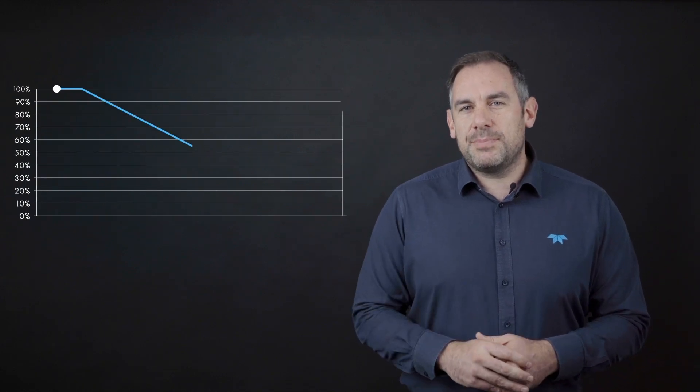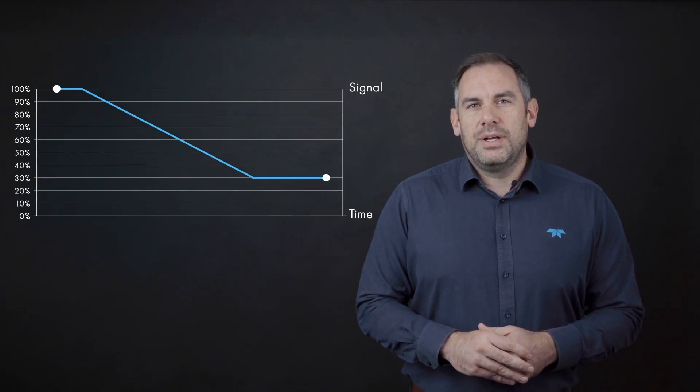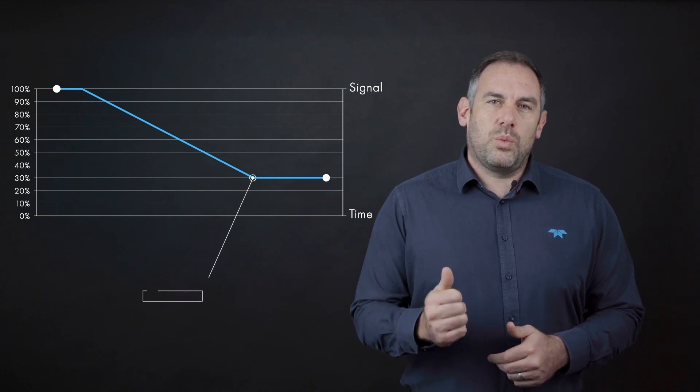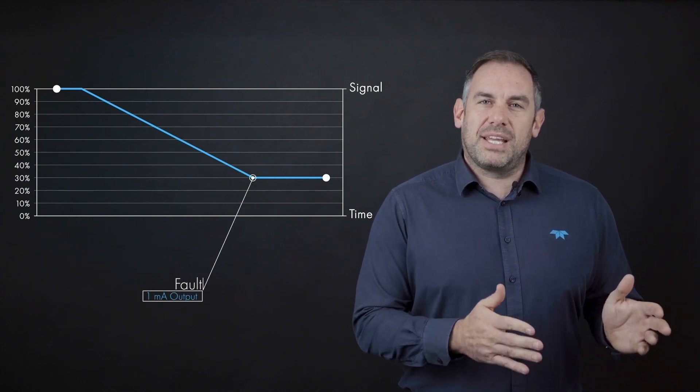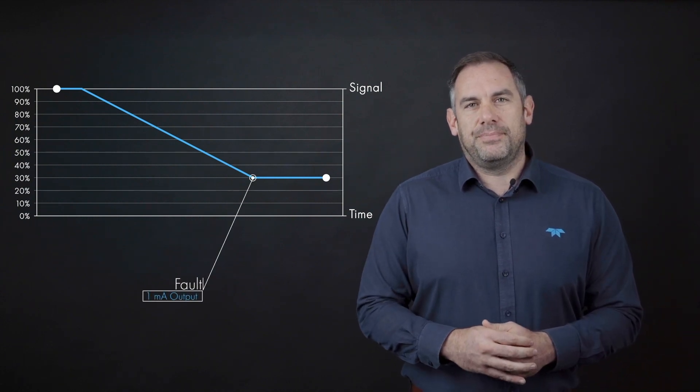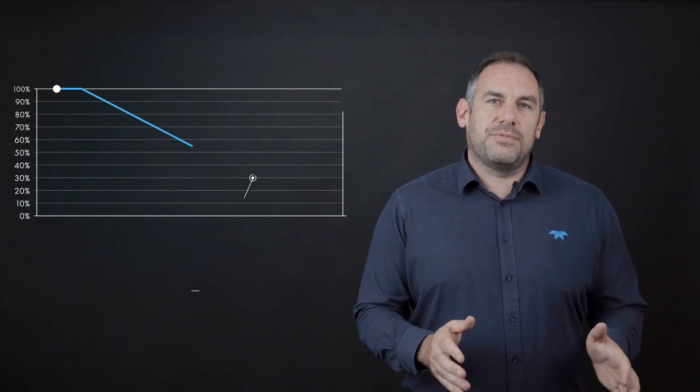If the device isn't cleaned and contamination continues to build, and the infrared absorption reduces to 30% of its calibrated level, then the device will go into 1 milliamp output, indicating a genuine fault condition. In this state, the device is no longer detecting and needs to be taken offline.